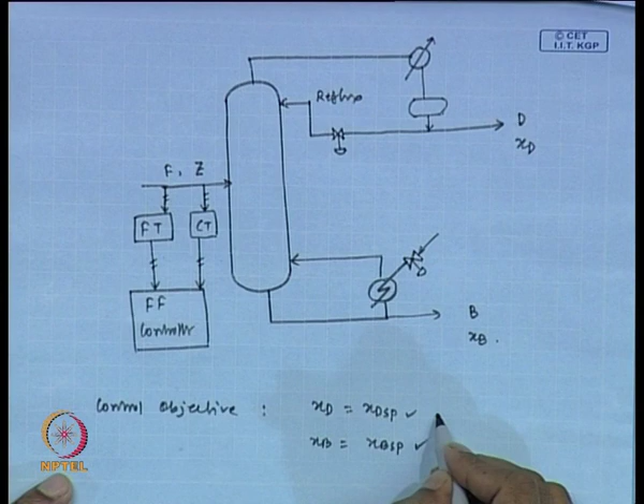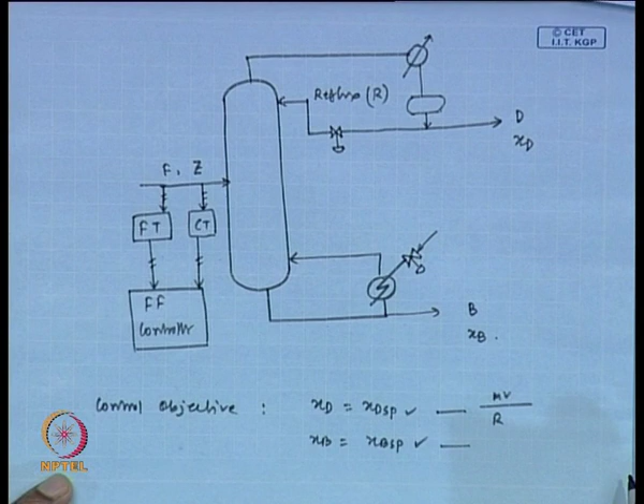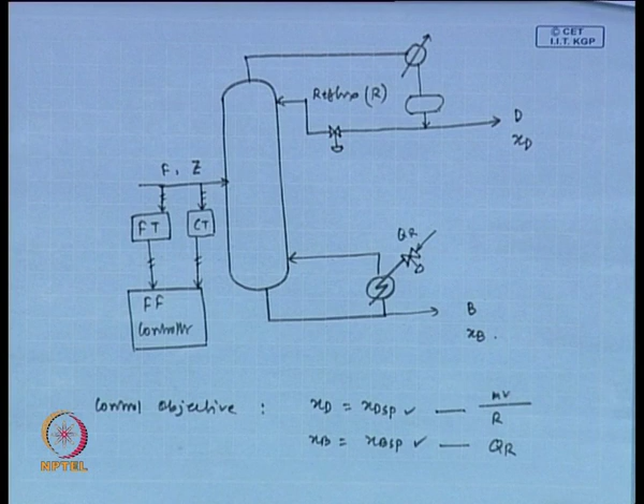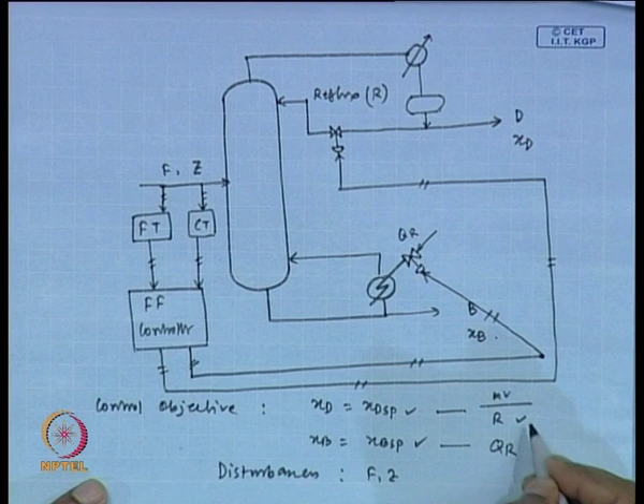Fine. For this top loop XD, the manipulated variable is reflux flow rate R, and for the bottom loop the manipulated variable is QR. QR is basically the reboiler duty. Then this is implemented for QR, and another one is for R. Fine. So, control objective is to maintain xD at xD set point, xB at xB set point. Disturbances are F and Z, and manipulated variables are R for xD and QR for xB. So, this is the feed forward control scheme for the distillation column. In the next class, we will discuss the theory involved with this feed forward controller. Thank you.